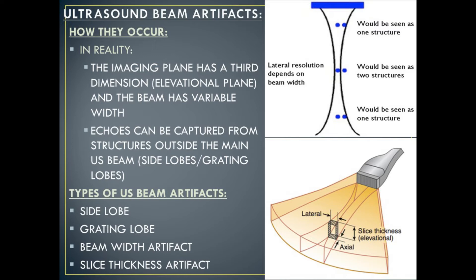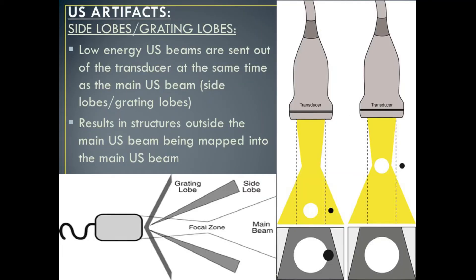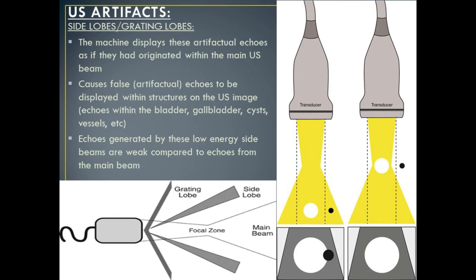Side lobes and grating lobes occur because low energy ultrasound beams are sent out of the transducer at the same time as the main ultrasound beam. This results in structures outside of the main ultrasound beam being mapped into the main beam. The ultrasound machine displays these artifactual echoes as if they had originated within the main ultrasound beam, causing false echoes to appear within structures that should be anechoic — most commonly the bladder, gallbladder, cysts, and blood vessels. Echoes generated by these low energy side beams are weak compared to echoes from the main ultrasound beam.